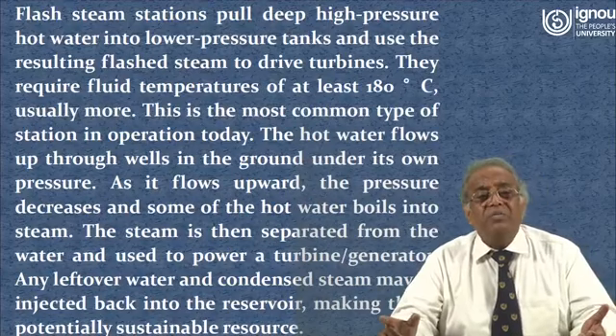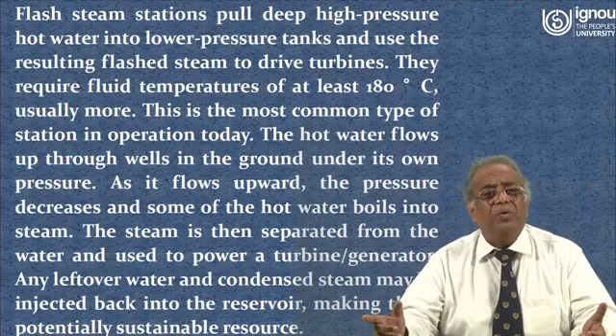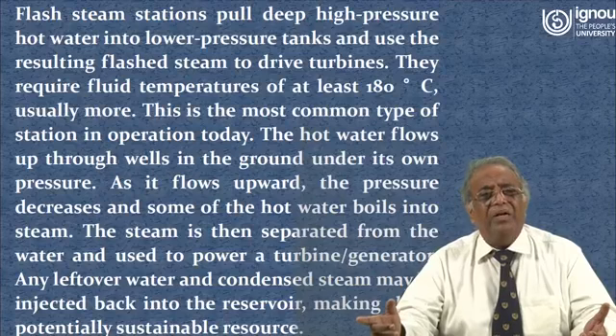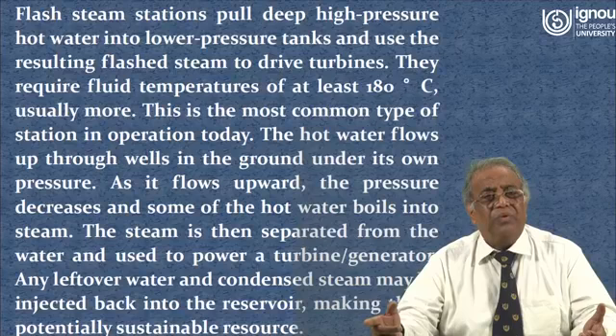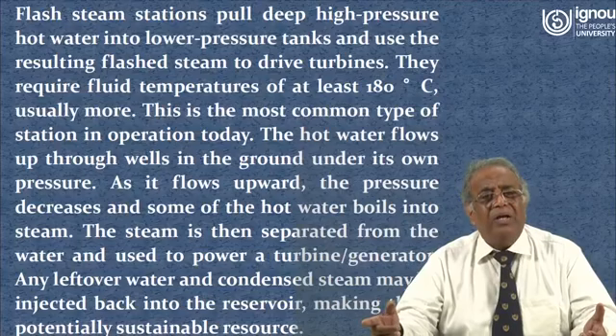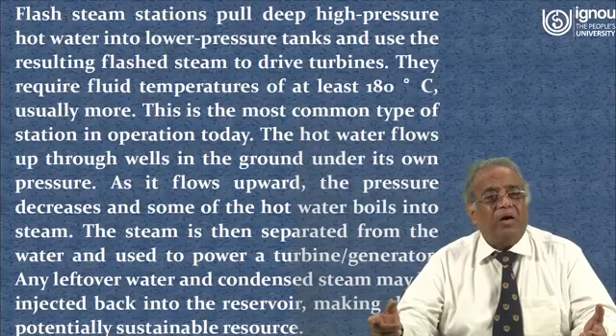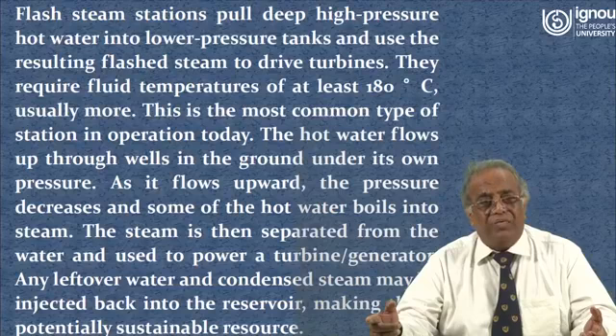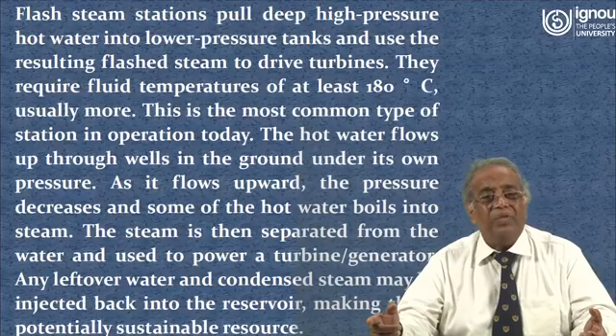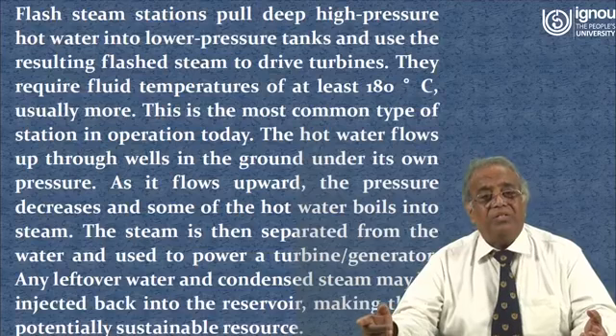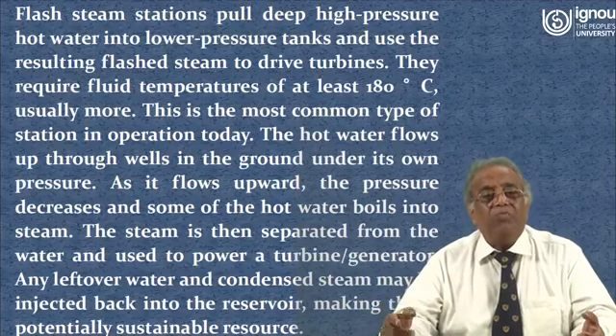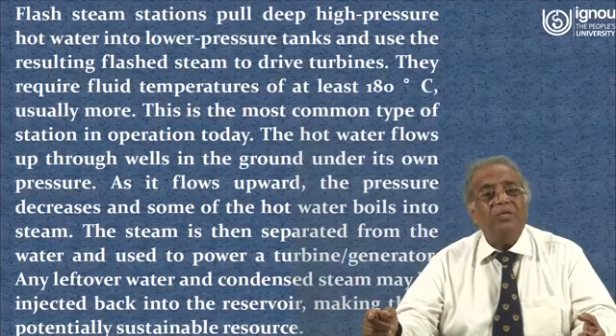Flash steam stations pull deep, high pressure hot water into lower pressure tanks and use the resulting flashed steam to drive turbines. They require fluid temperatures of at least 180 degree centigrade, usually more. This is the most common type of station in operation today. The hot water flows up through wells in the ground under its own pressure, and as it flows upward the pressure decreases and some of the hot water boils into steam. The steam is then separated from the water and used to power a turbine generator. Any leftover water and condensed steam may be injected back into the reservoir, making this a potentially sustainable resource.